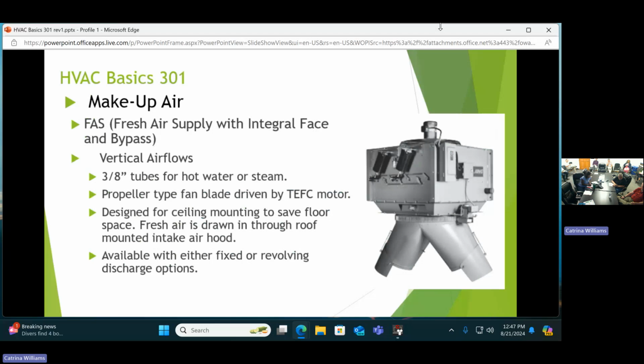But my example on that is, it's like being late for dinner. You're going to get the leftovers. It'll get to you eventually, but you won't feel the full draft as it hits you. So we offer that as a revolving discharge. See this gear motor over there? That drives this discharge round and round in a slow rotation. So it's constantly spinning around and just blowing air on a complete circle around that space. That's the revolving discharge. So it can either be fixed or revolving.